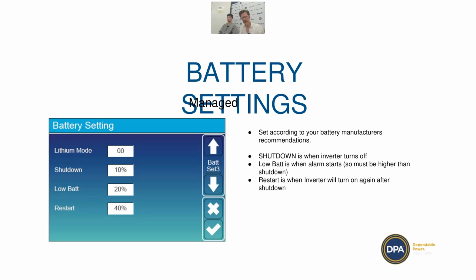The warning - shutdown is when it's going to actually switch off. Low battery is when it's going to start having an alarm. And restart is when it's going to start producing AC power again. It will still charge the batteries from the PV while it's shut down, but it's just not going to provide any power. Usually it's a good idea to have the restart value set reasonably high so the batteries don't flip in and out between states, and so they get a reasonable charge before the system starts again.